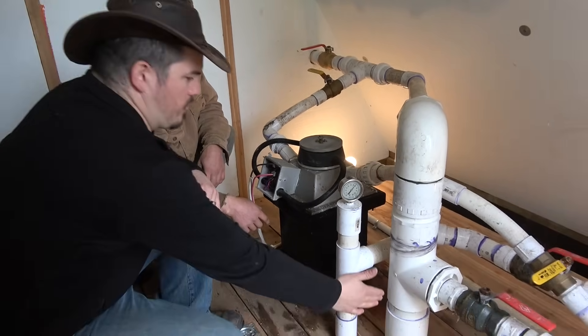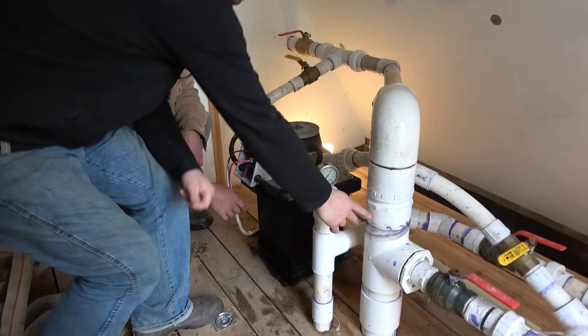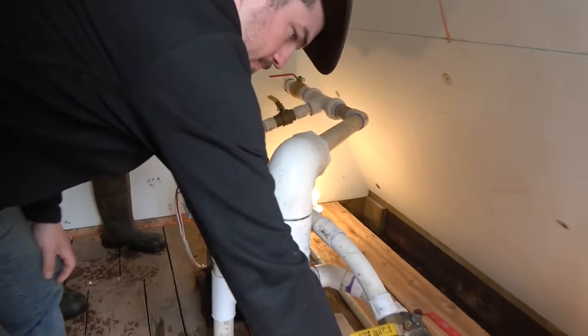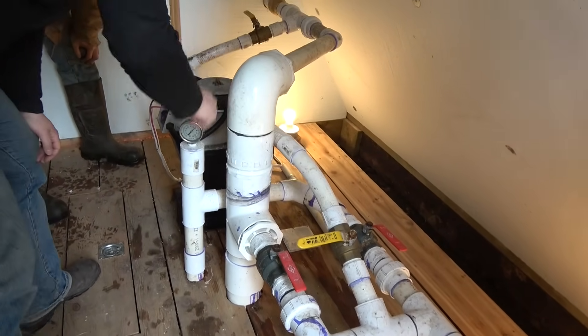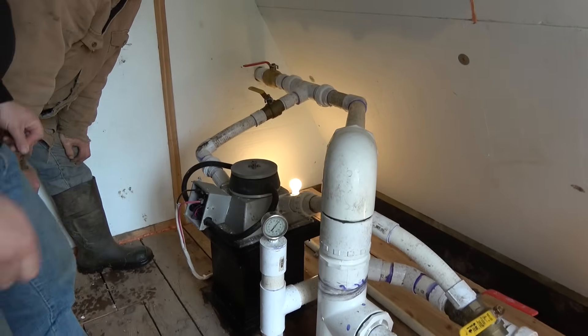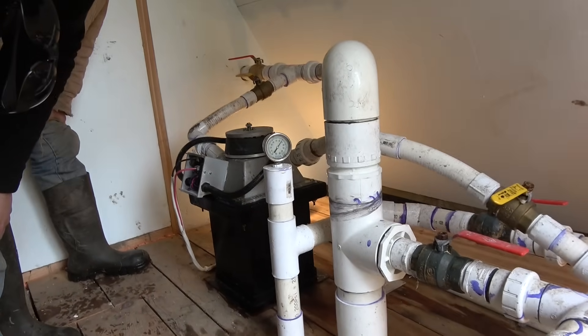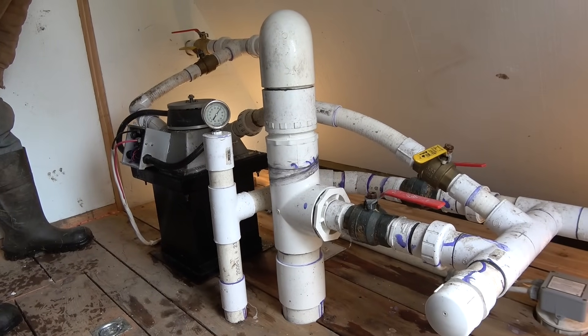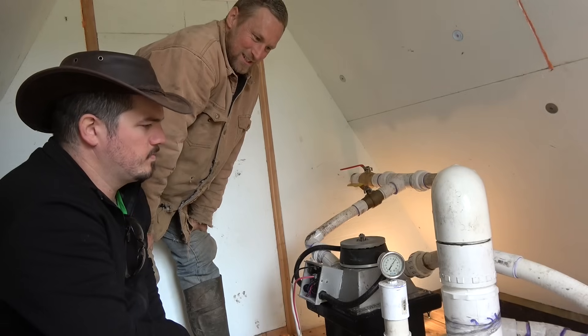This is the main water input to the machine. The water comes in and can go both ways — over here and up through here once the valve is on, or down through the other side. This is the static pressure in the water system, reading about 65 psi, but that gauge is wrong — there's a special gauge that displays incorrect pressure.